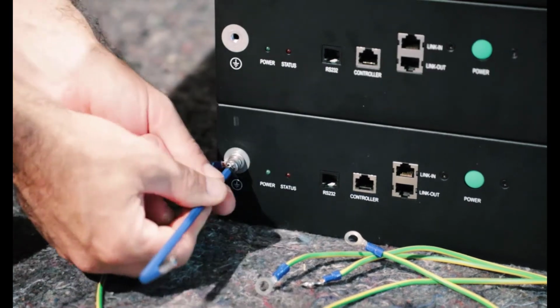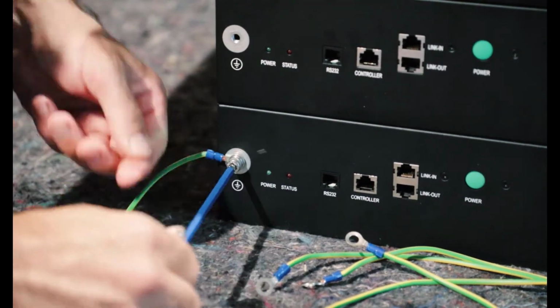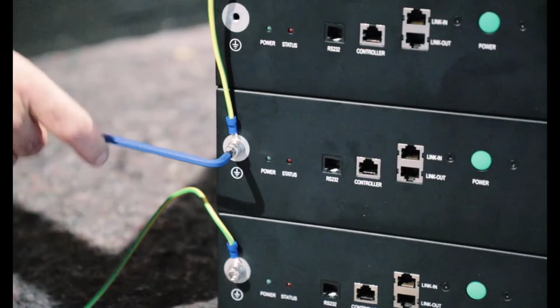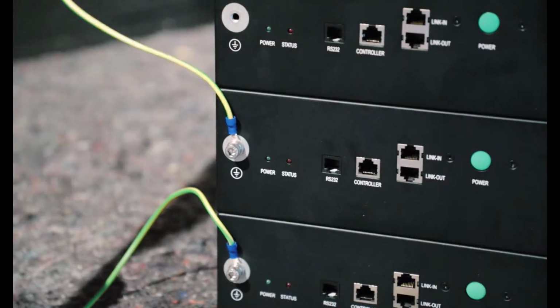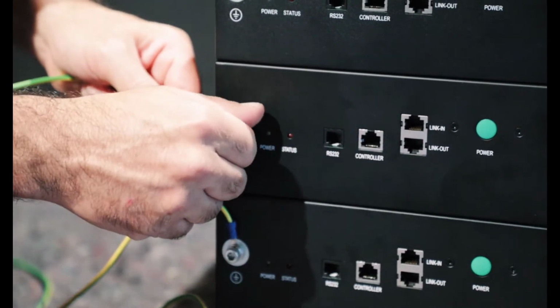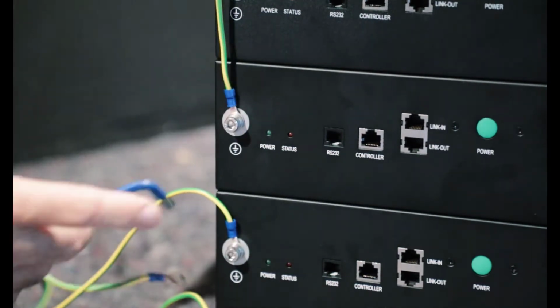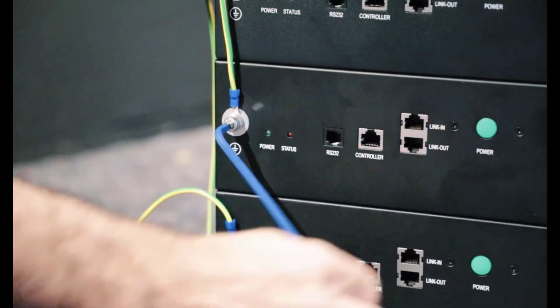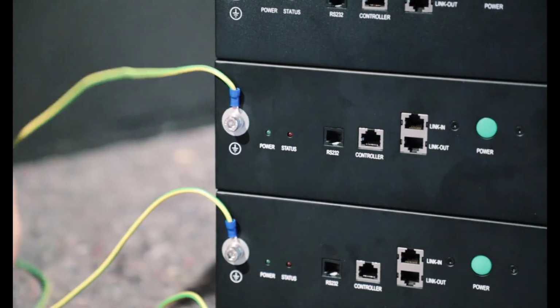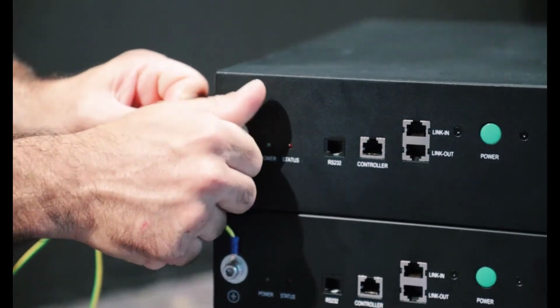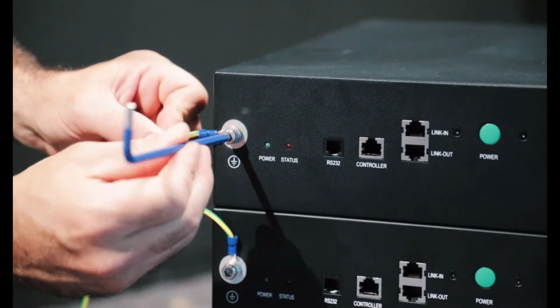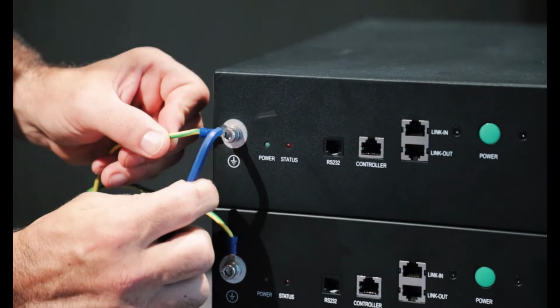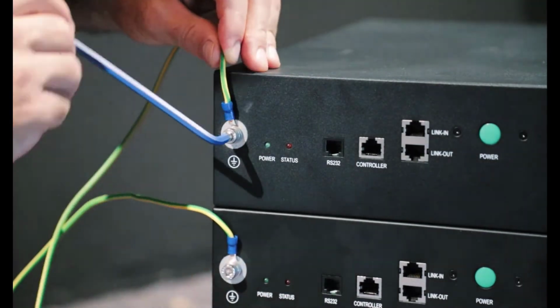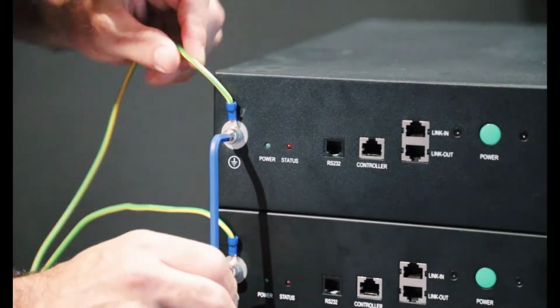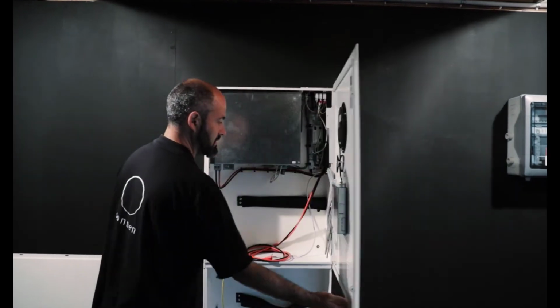Now each one of these batteries is rated at 2.5 kilowatt hours, that's total capacity. Usable capacity is 90%, which takes them down to 2.25 kilowatt hours. They use the CAN bus protocol, so what this means is that you don't need to worry about balancing voltages when you install them. They can simply be stacked in and added to at a later date if the customer wants to expand the size of the system, because they all reference the voltage and basically look at a cascading effect. So as they charge up, the one with the lowest voltage will always charge first.